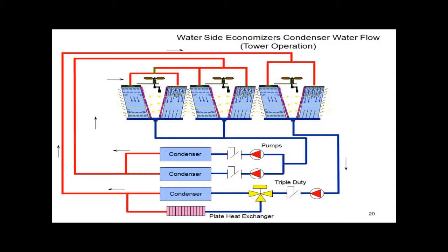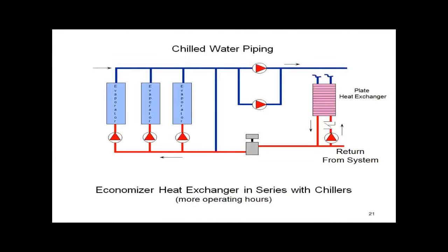But this is going to catch people by surprise sometimes, and it's something we need to be trying to help people understand. Now, when you go to integrate, what does this mean? And I want to caution you a little bit. I've flipped over now to the chilled water side, the chilled water piping. This is the cold water piping, the 12,000 BTU per ton side. I'm talking in terms of the return water, 45, 55, whatever numbers you may be looking at. And what I want you to realize is, in order to integrate the water side economizer in series with the mechanical cooling, I have to install the plate or the water side economizer on the return water, on the return chilled water. So with this particular slide, let's say your return chilled water is coming back at 56 degrees. Then I take the economizer and I knock the 56 down, let's say, to 53.